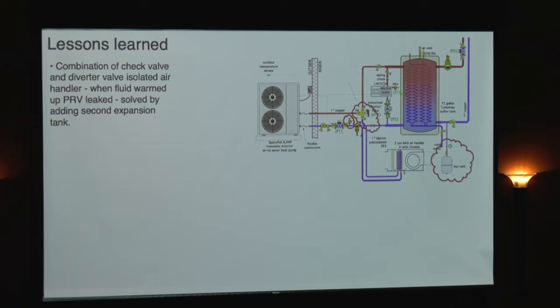Lessons learned. I made a mistake. I didn't see it coming. Here's where the expansion tank is, okay? Over here, here's that 3-way valve. Now, in the cooling mode, if we look at this line here and this line here, that line is blocked. In other words, there's no way this fluid can communicate with that expansion tank through the red line.